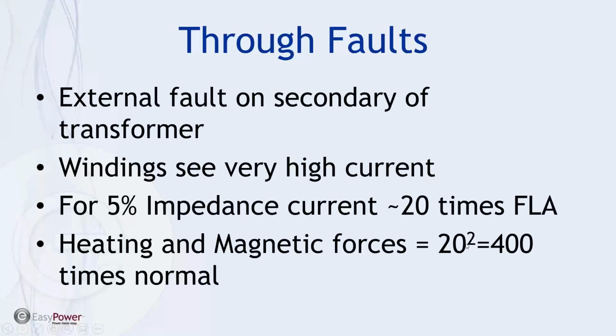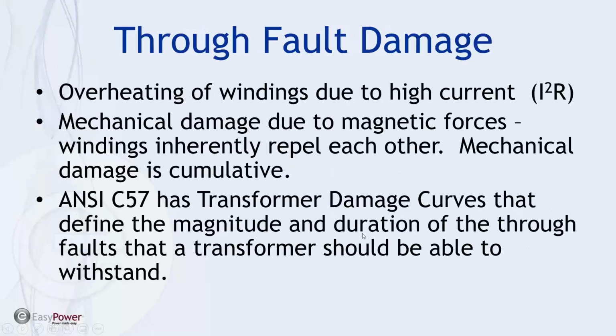And this especially is an issue when we're talking about heating and magnetic forces, because they are based on the square of the current. And so for current that's 20 times the full load current, the forces from heating and magnetic elements could literally be 400 times what normal stress would be. So through fault protection, again, prevents overheating of windings due to current.